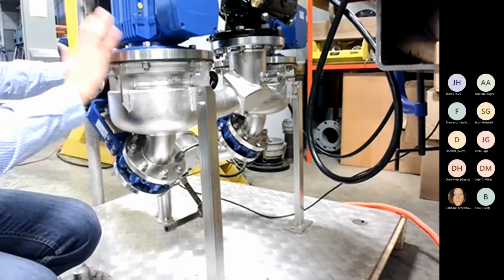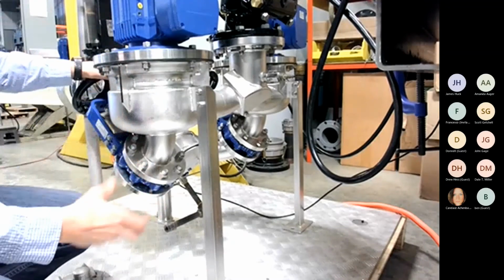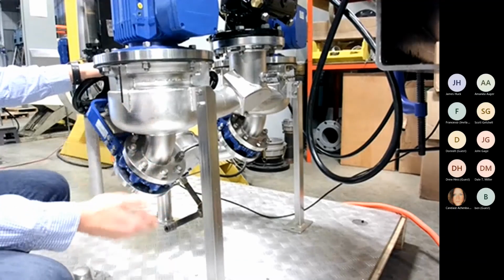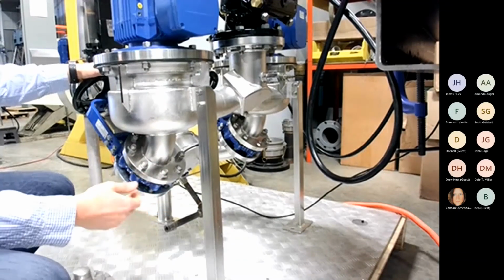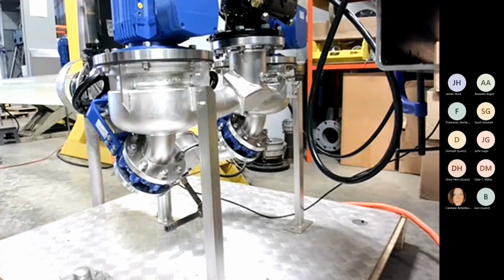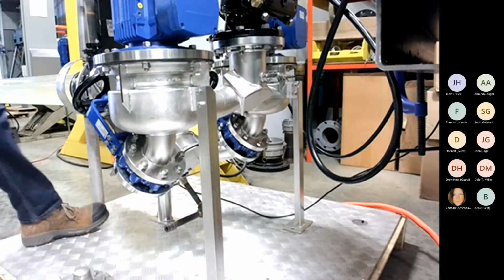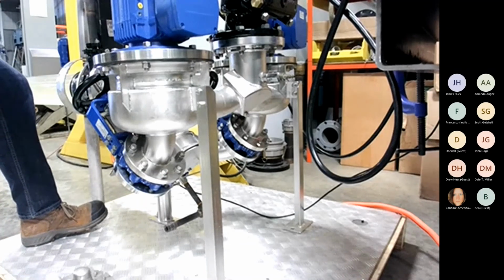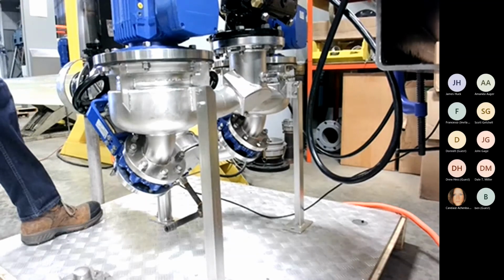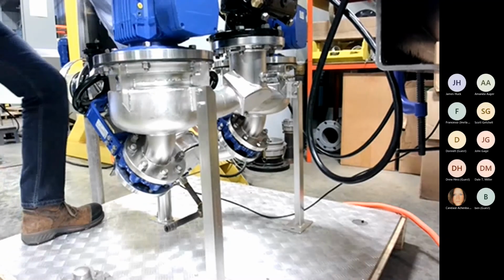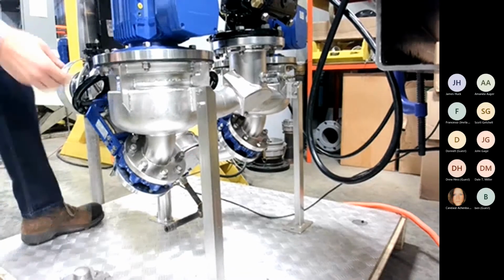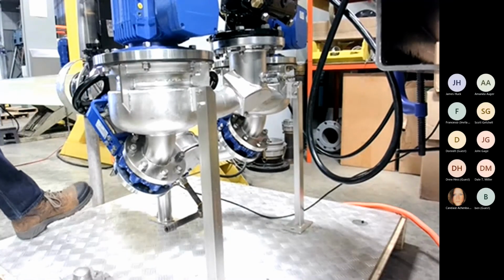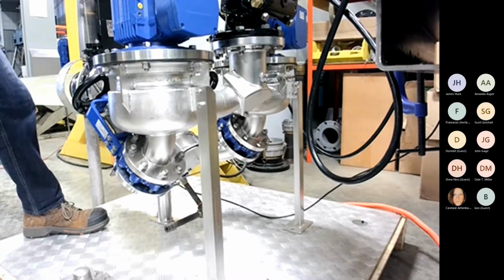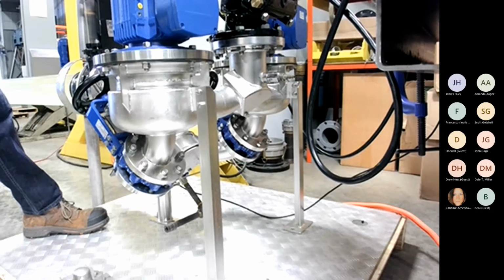What you would want to do is if a large particle came into the network that was too big to go up to the pump - like a large brick, large stone, piece of wood, things of that nature - it's never going to get to the pump, so it's never going to damage the impeller or the pump, it'll stop in its tracks and sit safely down in this environment. This would be one of the maintenance intervals we'd recommend: when you get this installed, maybe in the first month, you shut down these two isolation valves, shut this main valve down, dewater this section of pump, and remove the stone trap cleanout. Now you can access the large particles that are in there, measure the amount, know how much you accumulate over that period of time, and adjust your maintenance intervals around the amount you find in there.